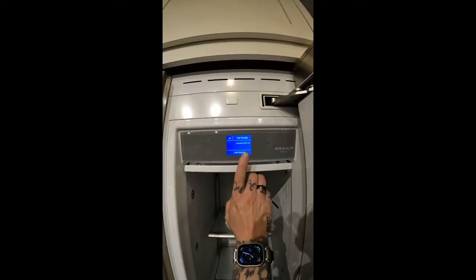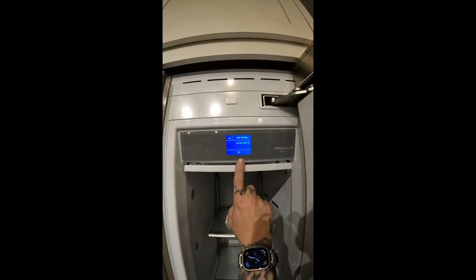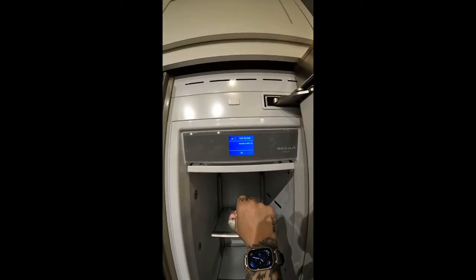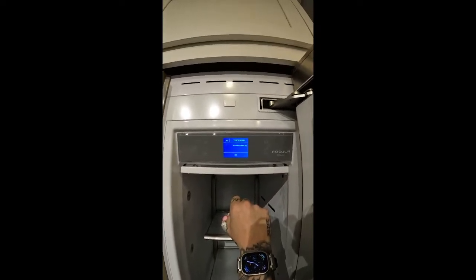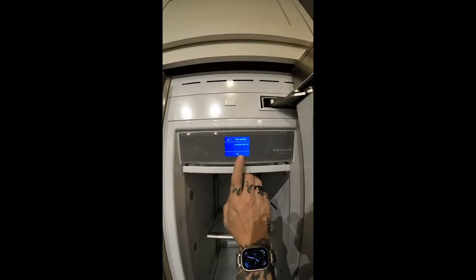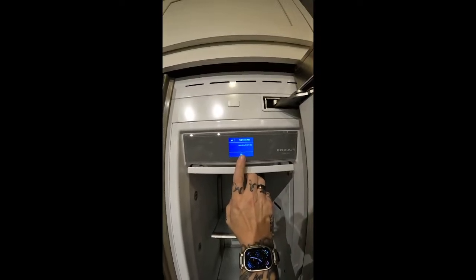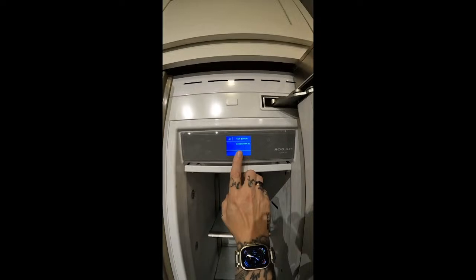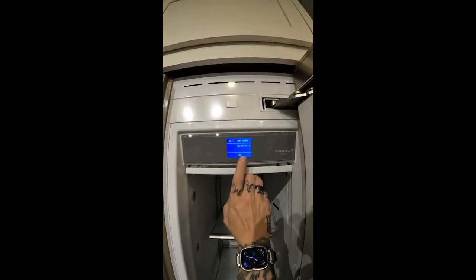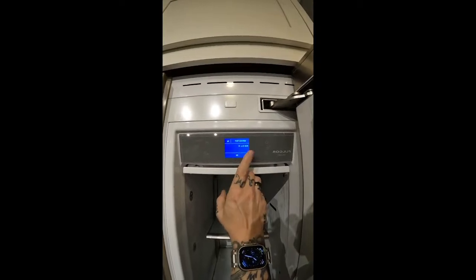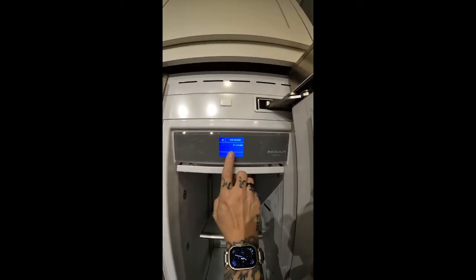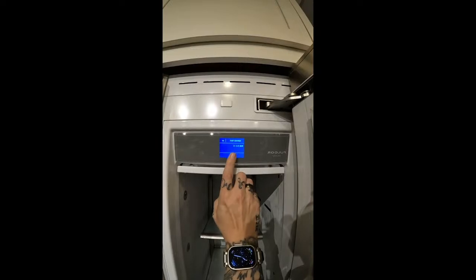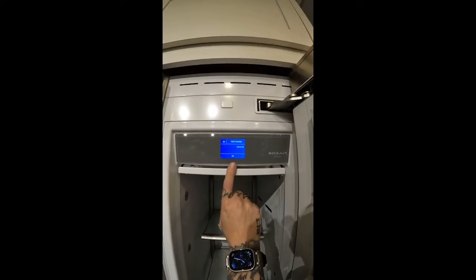There's a few other things that I would go through service mode for. Manual clean will tell you everything you need to know about your ice production and water flow throughout the machine. But service mode will get you to your fans, your heaters, and a couple other things that you're going to want to check, like your compressors, because it's a longer service mode. There's a lot of legacy features like RGB. We do not have RGB lighting in our refrigerators.